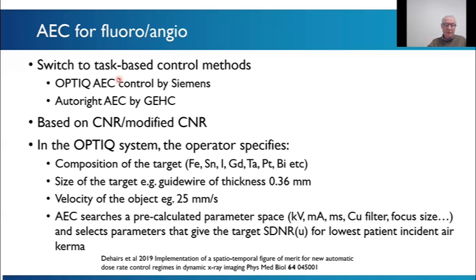For example, Siemens have the OPTIQ, and GE have Autoright. In the OPTIQ system, the operator specifies what you're looking at and what your target will be, the composition of it. So it could be iron or steel for a guide wire, or a tantalum marker in a stent. The size of it, so a guide wire thickness might be, say, 0.36 millimeters. The velocity of the object, for example, in cardiac, maybe 20 to 30 millimeters per second. And then the AEC searches some kind of pre-calculated parameter space and finds the X-ray factors that deliver the target image quality for the lowest incident air kerma.